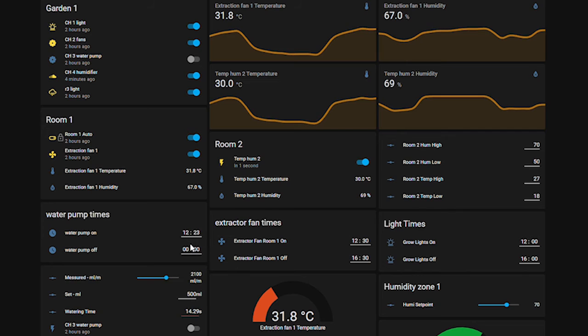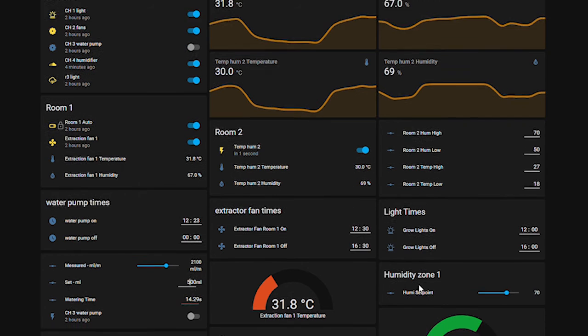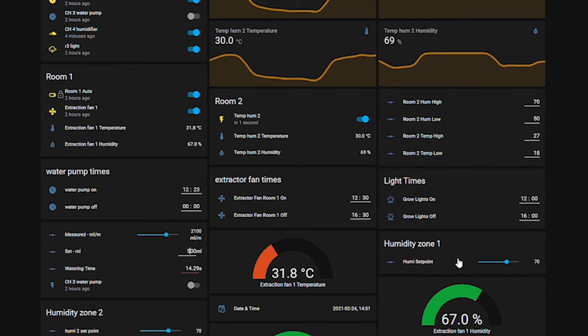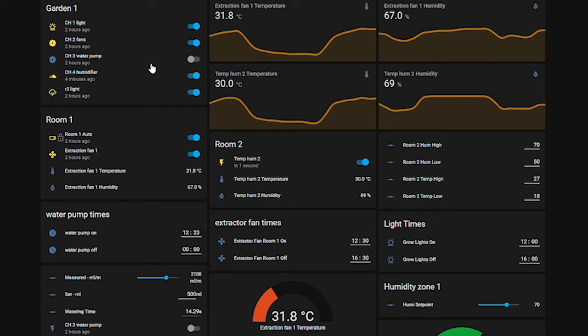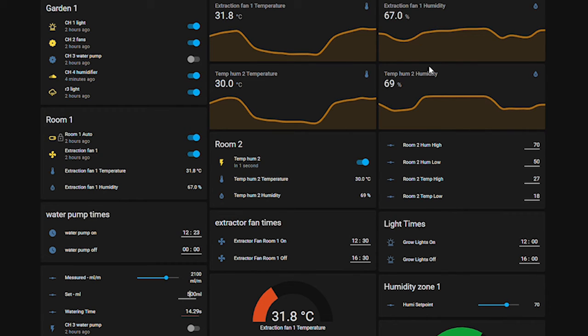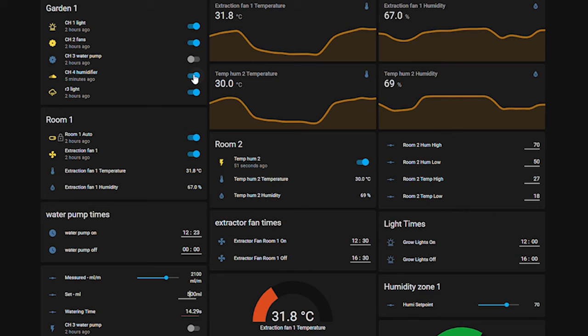So I've now set these new humidifier sliders where I can set the humidity I want in each zone. And what it does is the humidifier will switch on and off to try and maintain that zone. Currently it's set to 70 and it's trying to maintain 70. And as you can see from the history, it's more or less maintained it whilst we've been talking.